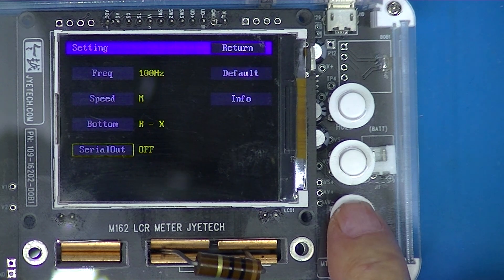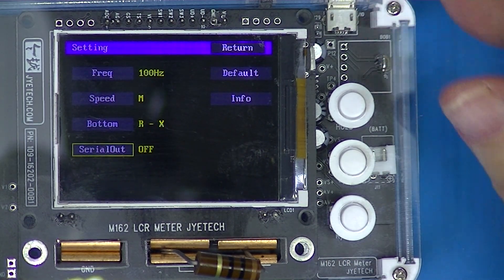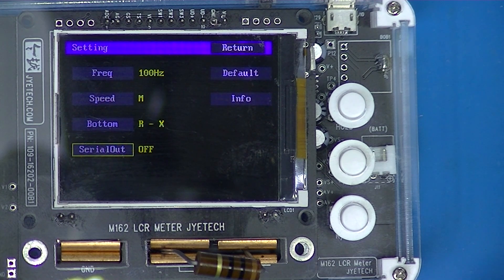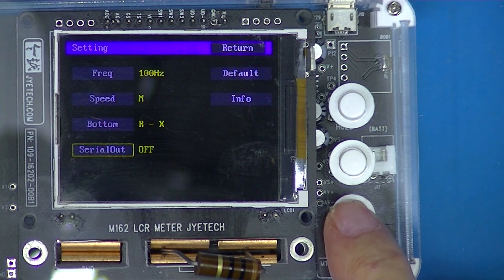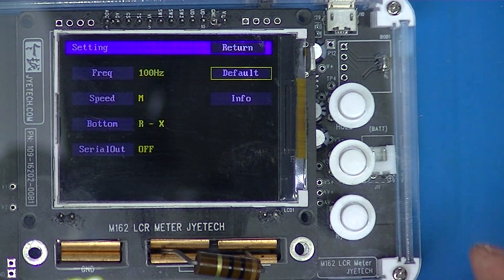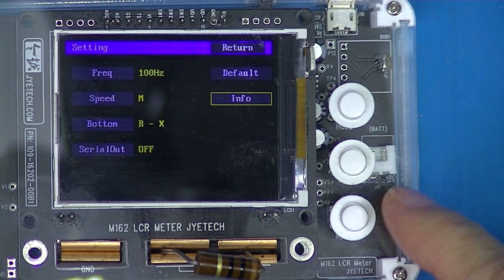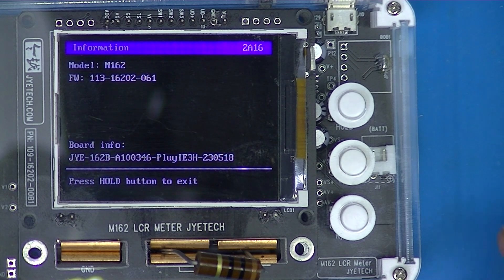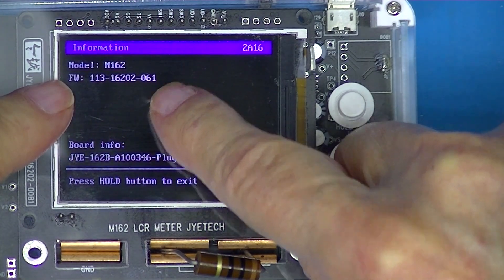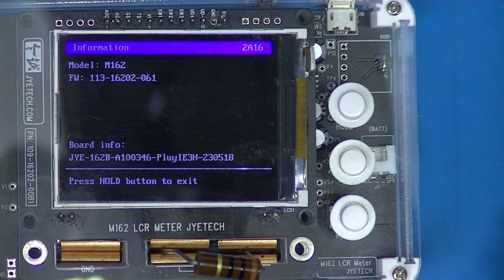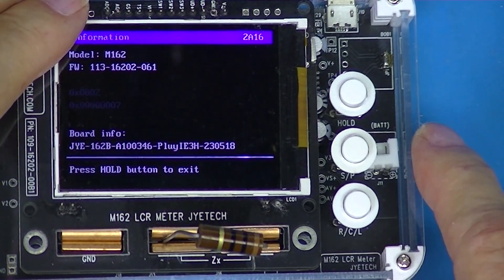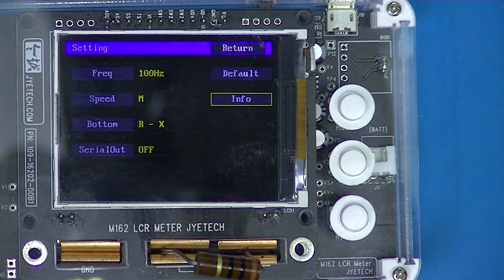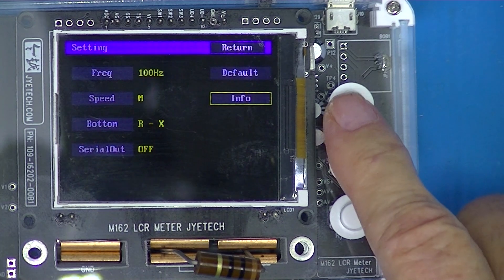Serial output lets you output through the USB port a string of measurement information if you want to record data. Default returns it to factory default, and information probably displays that second splash screen with the current firmware version. Press the hold button to exit — the third button is the hold button — and it takes us back, and the hold button should also exit the menu.